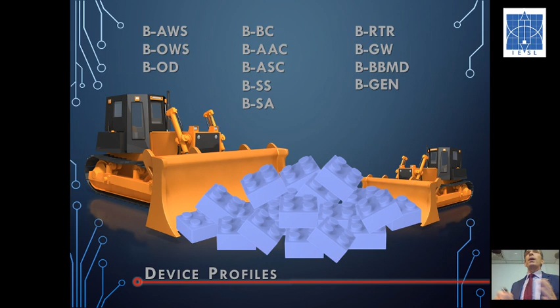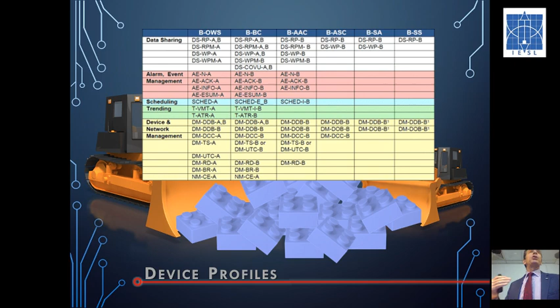Let me expand on the controllers a little bit, as Jacob touched on. From your right-hand side, we have simple smart sensors and simple smart actuators, and as you can see, they only have a few BACnet properties or services to share. Then as we move across to your left, we move into the application services, and in that red bar there, they start to increase in their service capabilities. Then across again to the advanced application controller, even greater services are available, and in particular, they have scheduling in there. Then if we move across to the BACnet building controller, which is the highest profile of services provided, it gives us the greatest amount of information exchange between devices. And then finally, these are profiles that allow us to communicate across multiple networks.